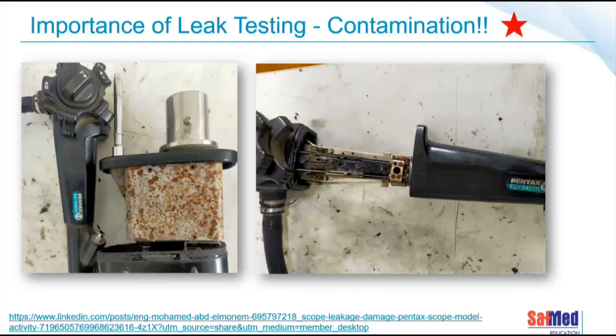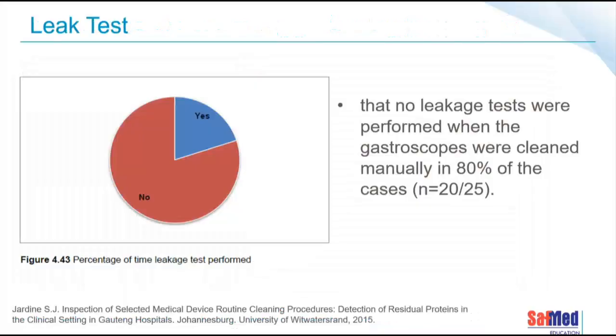Looking at this image over here, this is some form of contaminant that's ended up inside a scope. And you would not know that because you would not be able to see it. Imagine somebody doing a scope on you with this contaminant inside the scope. Is that corrosion? Is that feces? Who knows? In research conducted in the South African setting in 2015, which was a while ago, but I bet that it's probably relevant still today, in 80% of all of the cases where a GI scope was cleaned manually, a leak test was never performed. I wonder what those results are in your hospital.